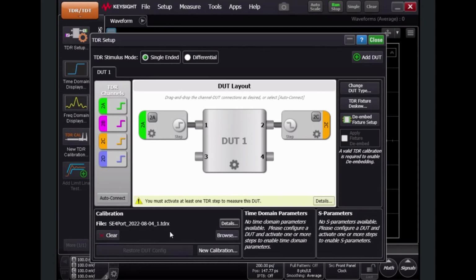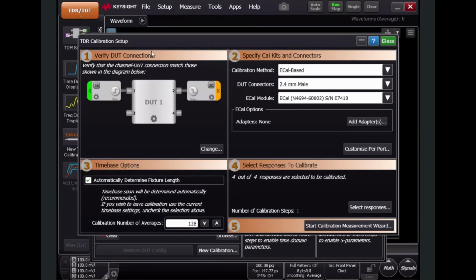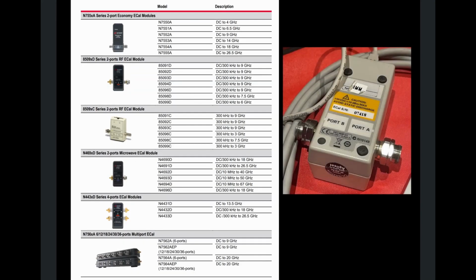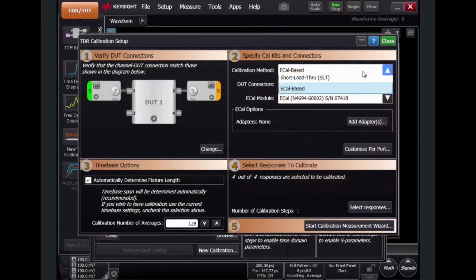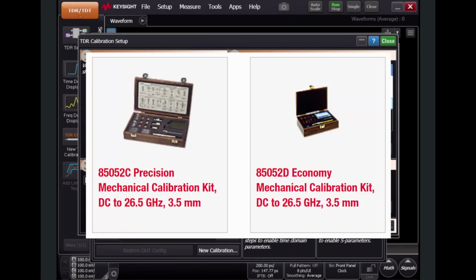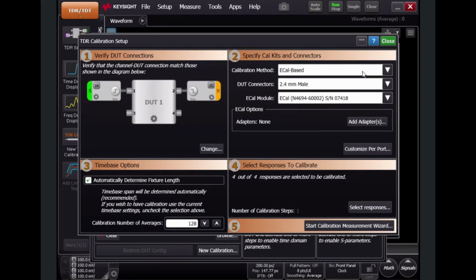I'm going to do a new calibration and verify DUT connections. You're going to verify this is how you're going to be connected to your DUT, and that's how we're going to do it. We're using the ECal, the electronic calibrator. You do have the option of short open load through, or the short load through hardware to do that, but I'm not using that. I'm using the ECal because it's a heck of a lot faster and highly recommended because it just makes life a lot easier. You don't have to keep connecting and disconnecting.